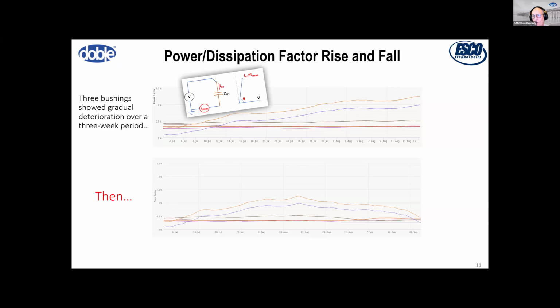If you look at how power factor or dissipation factor works inside an insulation system, you're essentially measuring the angle between your reference voltage and the applied voltage and current going through the asset. That angle is the power factor angle, and the number is usually very small, based on the cosine of that angle, typically below 1%, since that's the power transferring through the insulation, not down the transmission line.